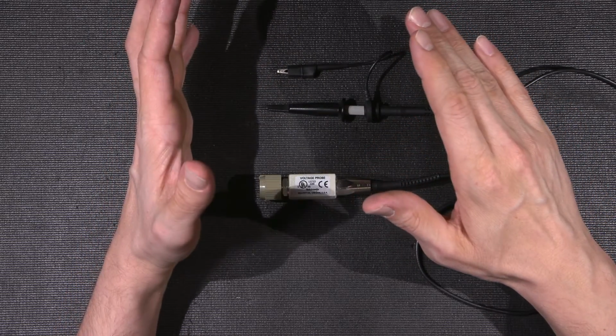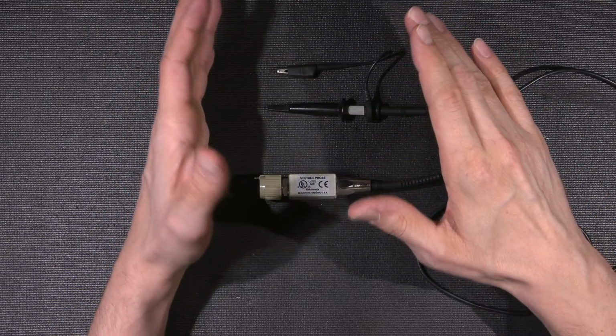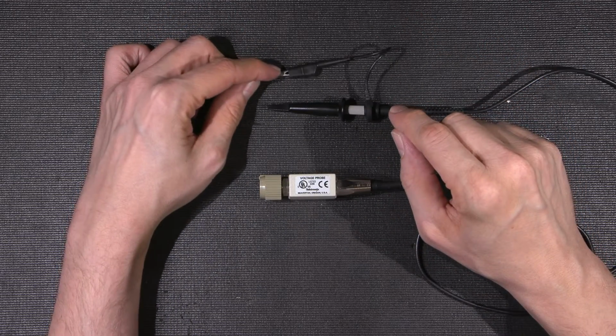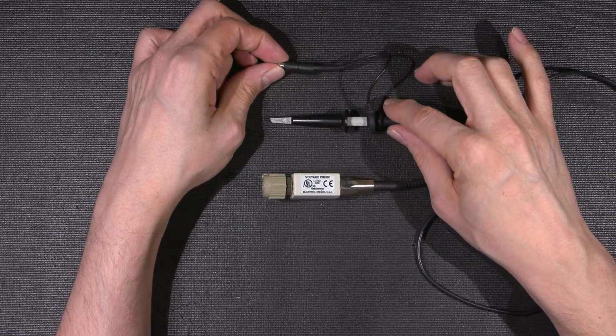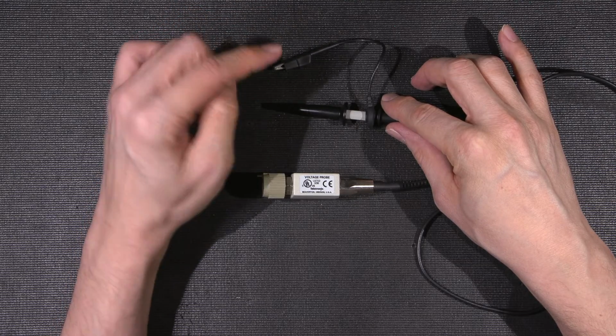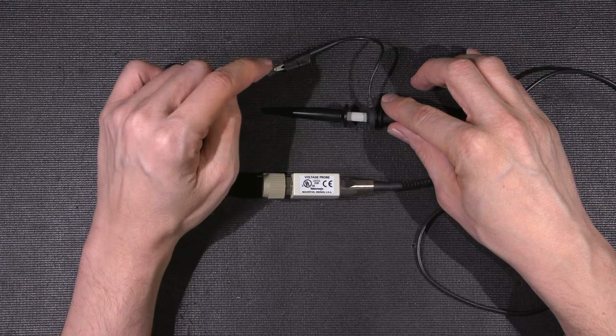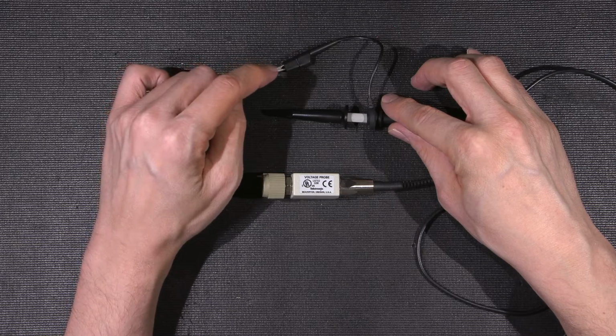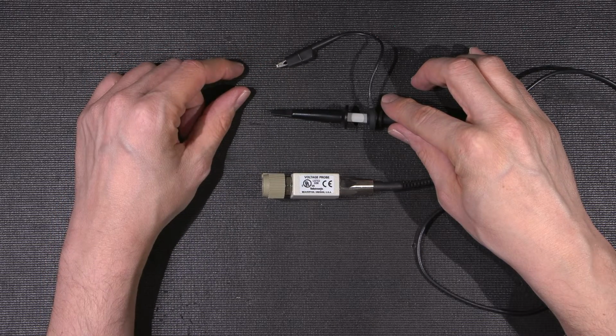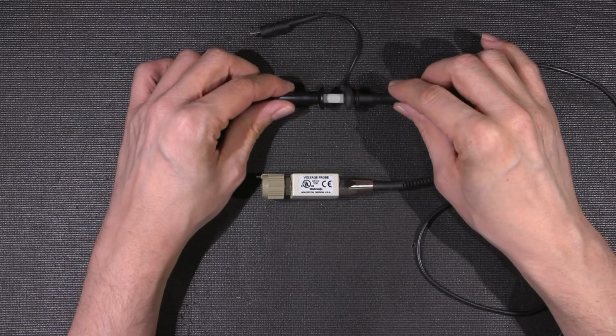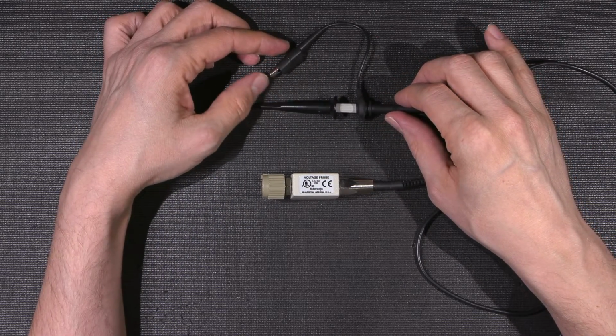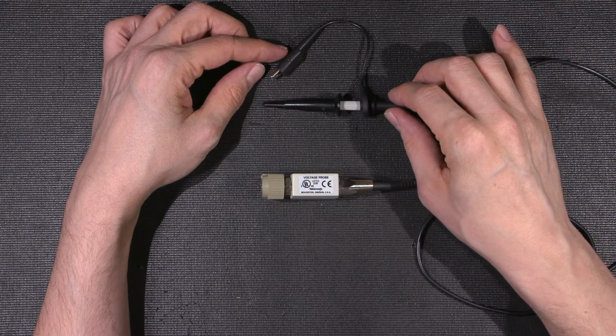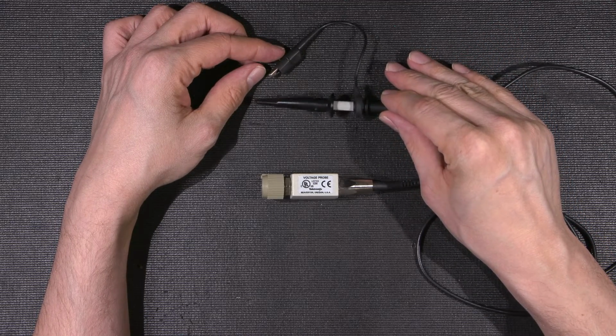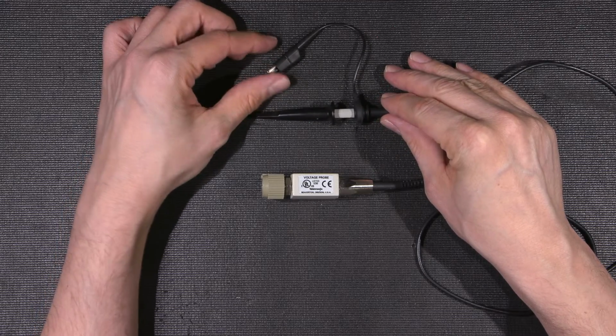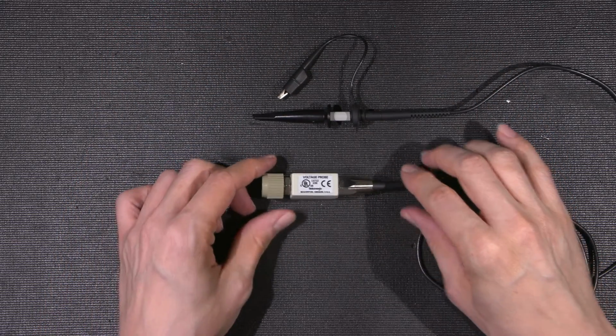Rule of thumb is if your oscilloscope plugs into the wall, chances are this lead is directly attached to the safety ground. And never forget, in many cases, that safety ground is attached to the neutral in the breaker panel. So technically this is tied to the neutral side. There's a path to it. So you don't want to destroy any very expensive probes. You definitely don't want to take a chance in getting electrocuted or anything like that. So it's never a safe thing to do. So definitely do not try to probe the AC line.